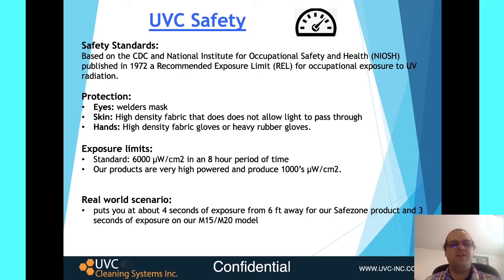The standard says that you are allowed up to 6,000 microwatts of energy in an 8-hour period of time, and our products are very high powered, producing thousands of microwatts of energy. In a real world scenario, you can be in the room about 4 seconds from 6 feet away using our safe zone, or 3 seconds of exposure using our M15 model. Both of our products have the option of motion detection as one of the features, and if you choose to use that, it is a very good tool to help ensure that nobody is exposed improperly.